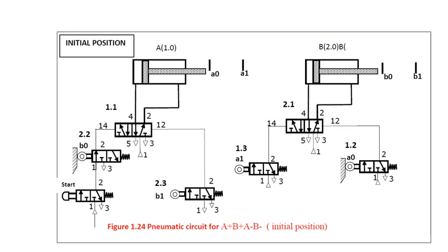So initially we need to draw two double acting cylinders, then two limit switches for each cylinder, and two memory valves, independently, which will control the double acting cylinders, and the limit switches are the input for the memory valves. And we have a start button. This will be the start button to start the cycle, and two limit switches for each cylinder to give an input signal towards the memory valve.